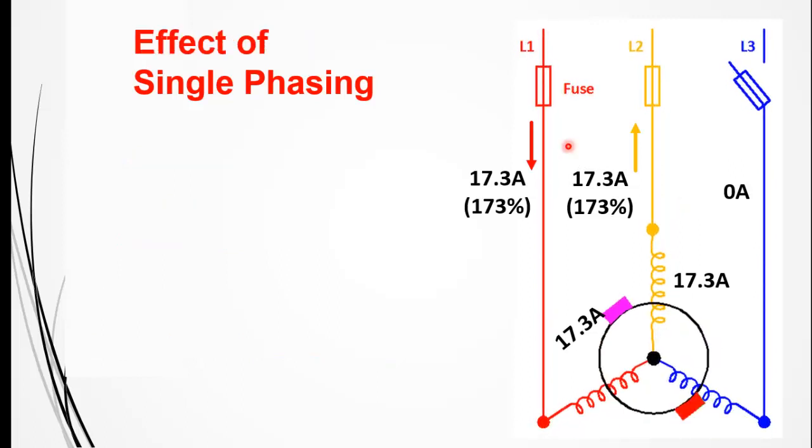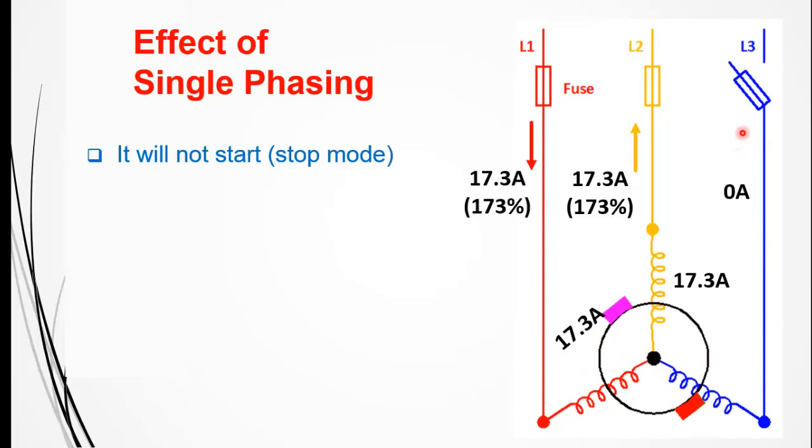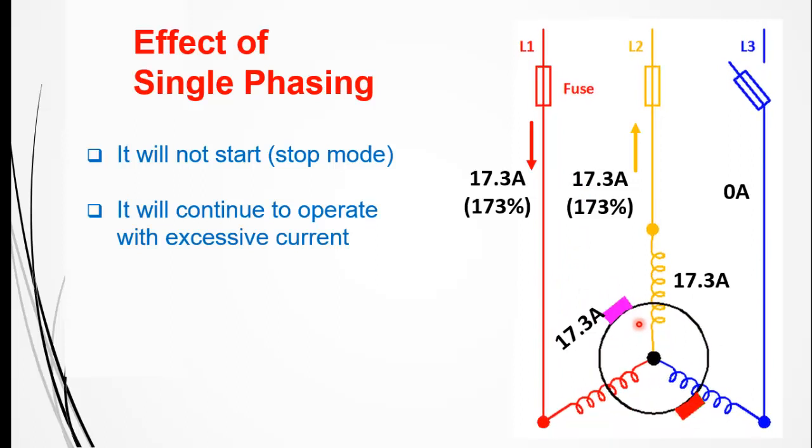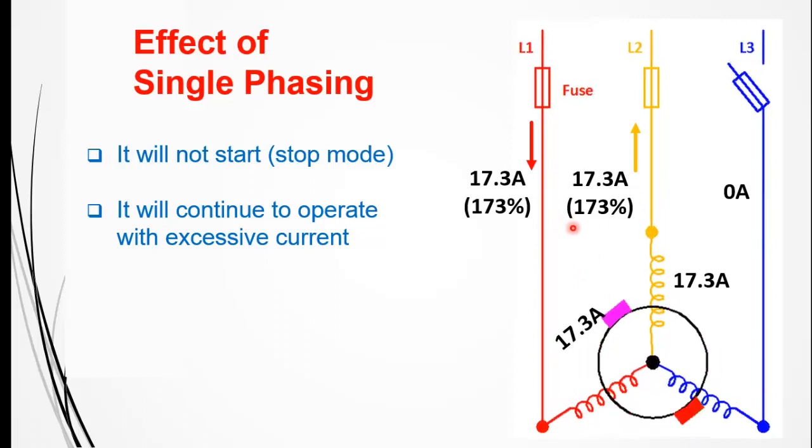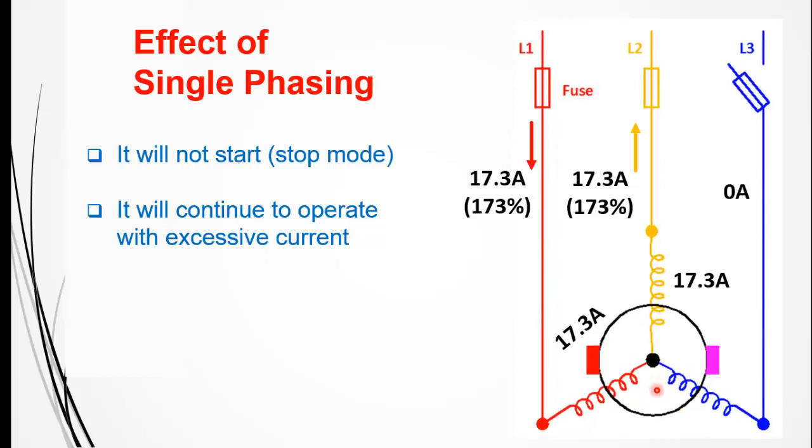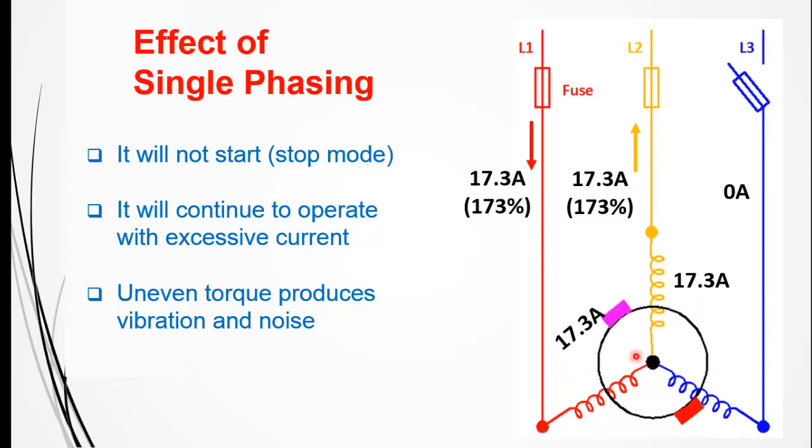At the end, I will discuss the effects of single phasing. If the motor is in stop mode and one of the phases is disconnected, the three-phase motor will not start. However, if the motor is already running, it will continue to operate on two phases but with excessive current, which is damaging to the motor windings. It will continue to rotate with excessive torque produced as a result of the excessive current that flows in the windings, which will cause the motor to burn. As the motor tries to produce excessive torque, it will cause vibration and noise, which is also very damaging.